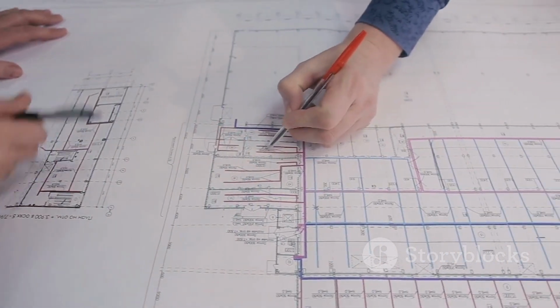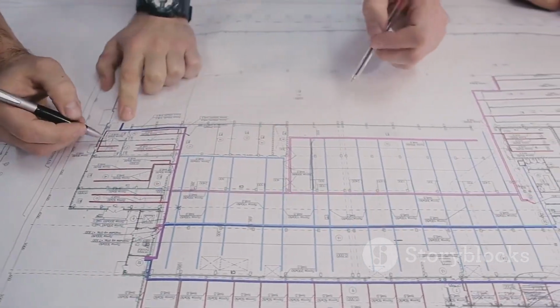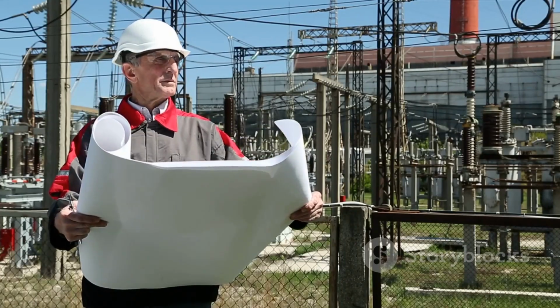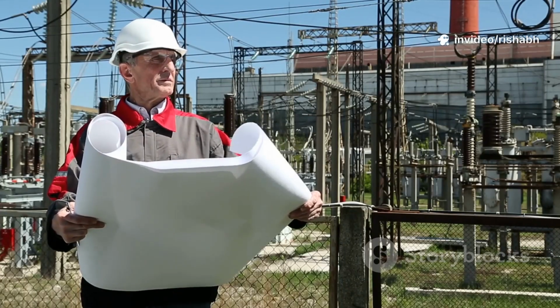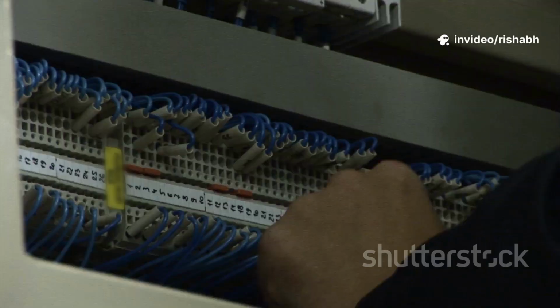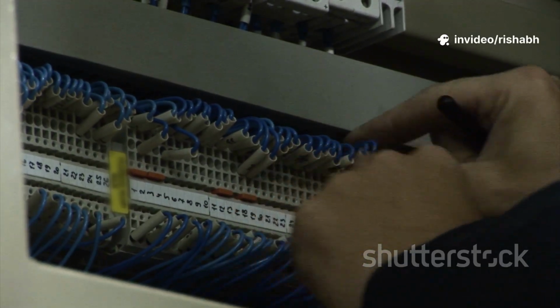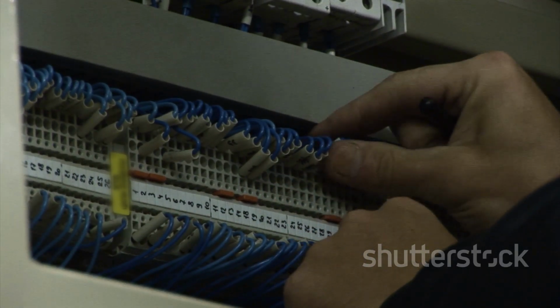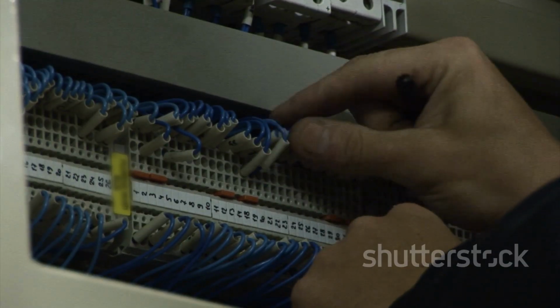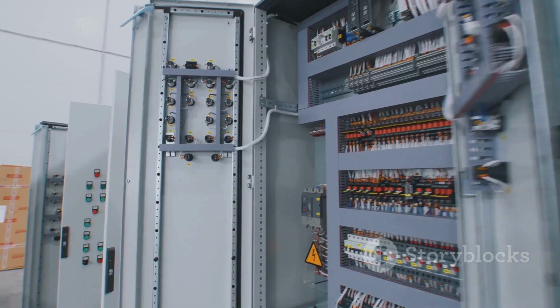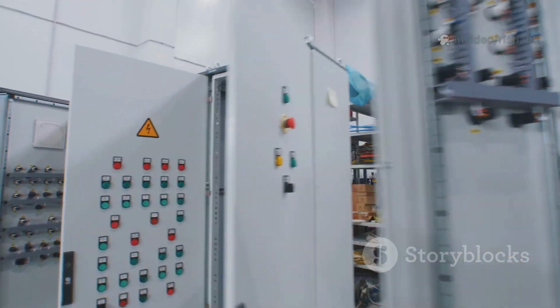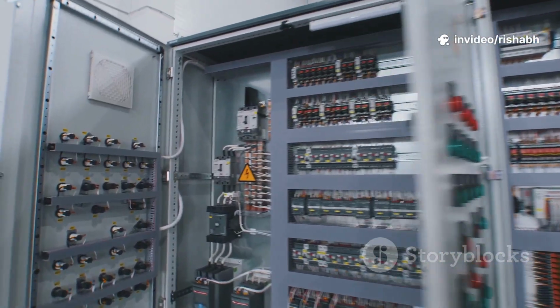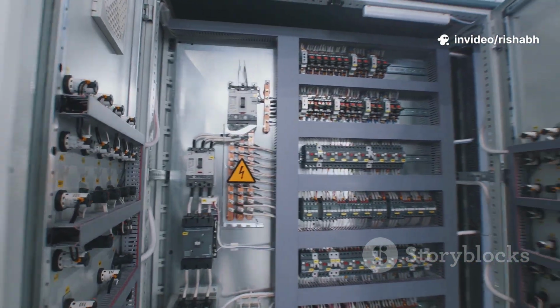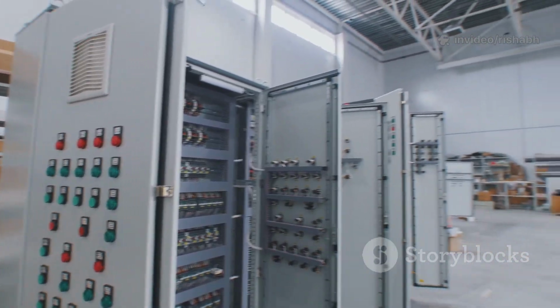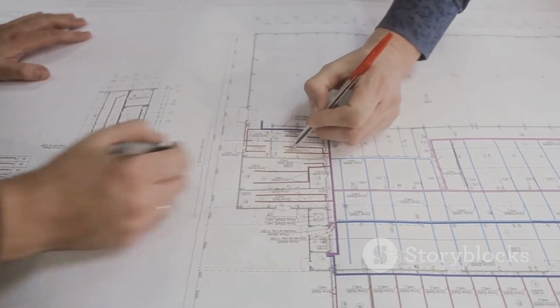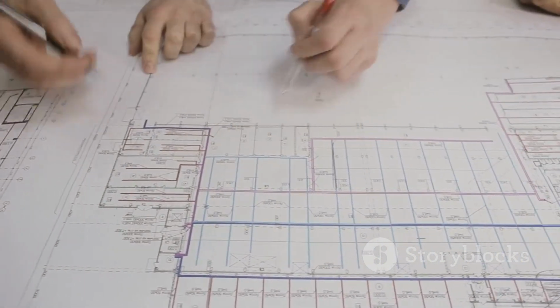Simultaneously, engineers create detailed interface drawings. These include the foundation plan, showing the exact location and loading of support points. They create drawings for the high voltage and low voltage terminal connectors, ensuring they will match the customer's substation bus bars. Details of the control cabinet wiring, cable entry points, and marshalling kiosks are meticulously documented to ensure seamless integration on site. Each of these drawings goes through a rigorous review and approval process.